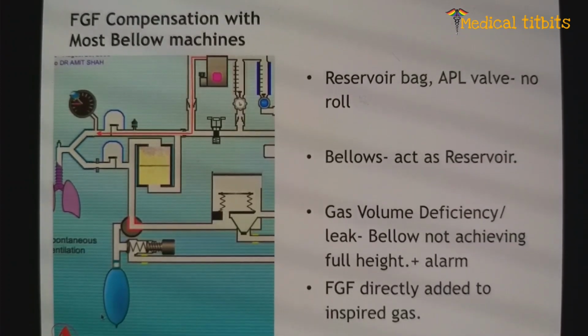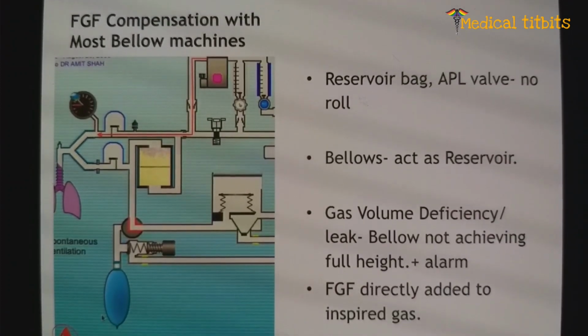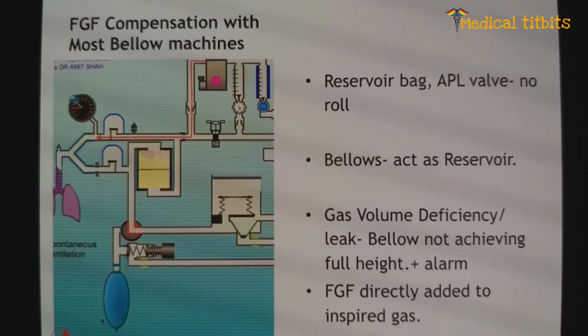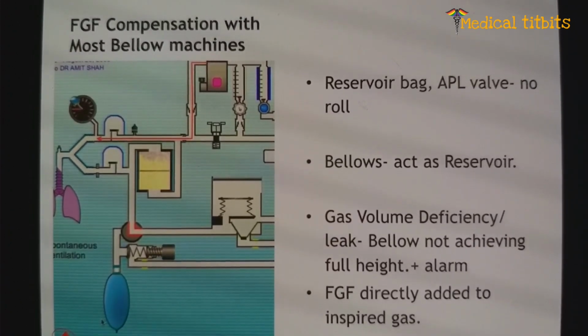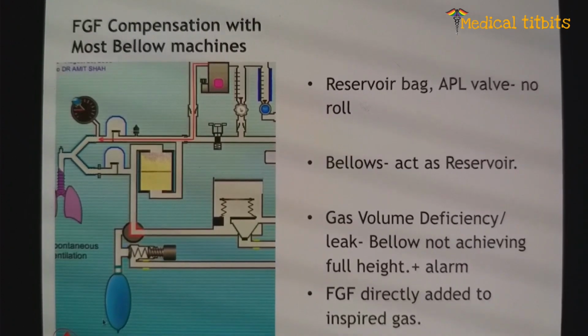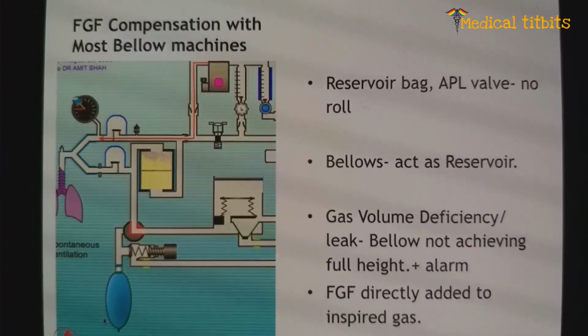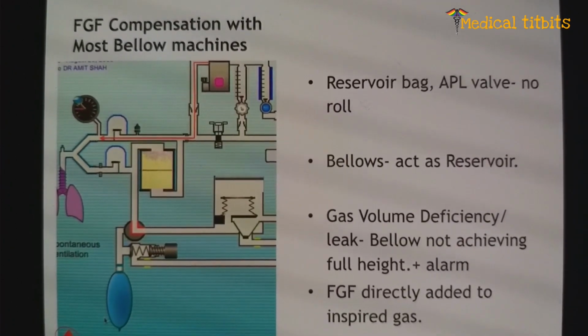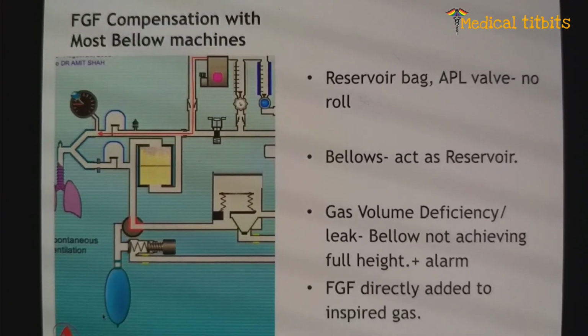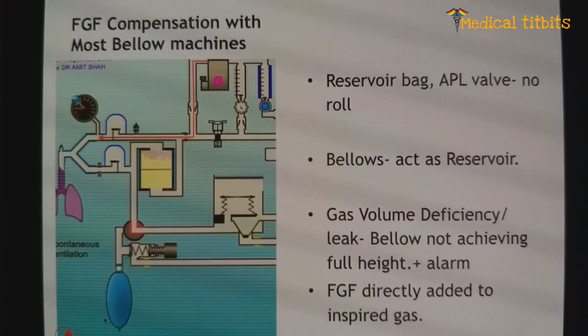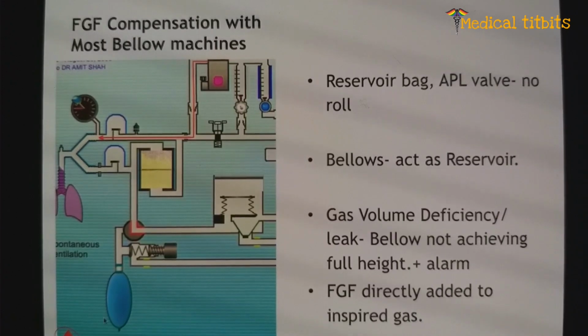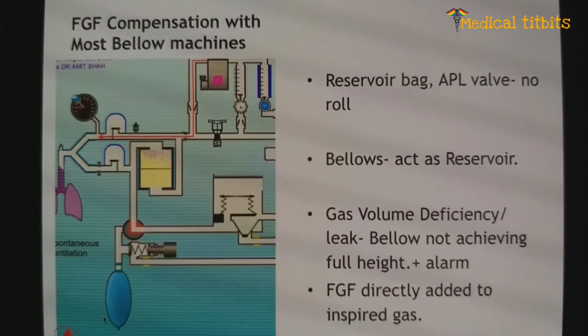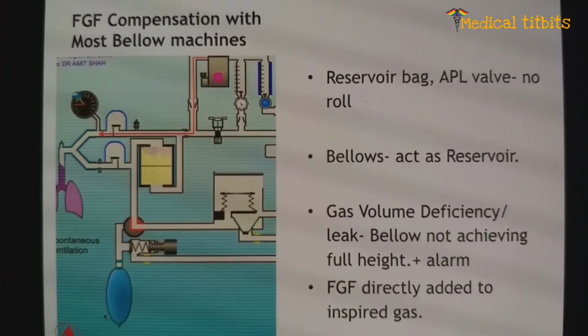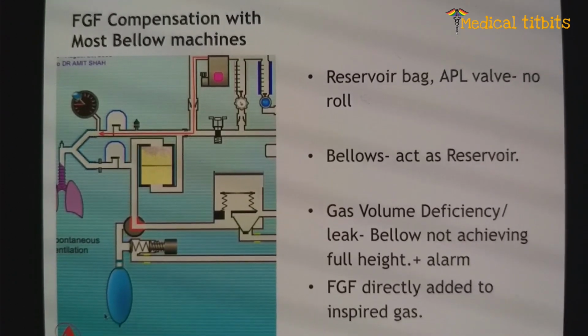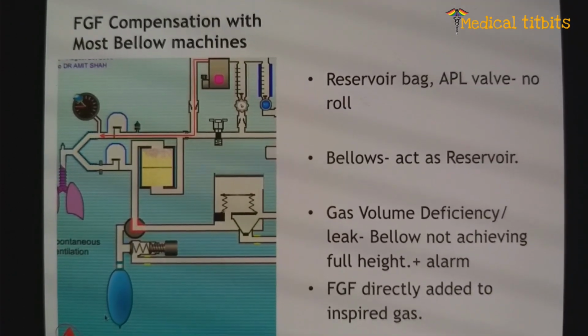So if there is insufficient flow or if there is leak, you will see bellows not achieving the full height. Bellows will continue to go down from a not so peak height. It will go down from a lower position. And also, of course, it will give you alarm. Here, a minor advantage: fresh gas flow is directly added to the inspired gas. So your reflection of changes in the inspired setting is slightly faster compared to the other technique.